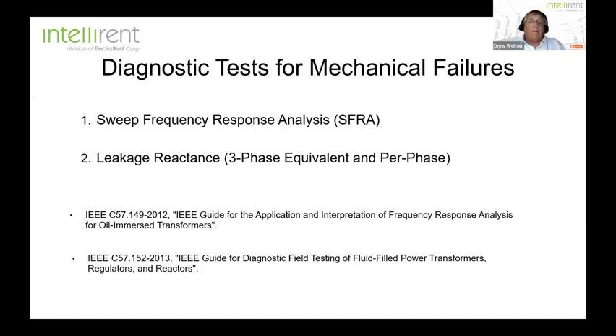All right, so let's say we've had a number of through faults and we've recorded this information, and we want to actually, during our next maintenance period when we're testing the transformer, see if there has been any physical damage associated with the transformer. And there's two types of tests you run for looking at mechanical failures. One, of course, is the SFRA, sweep frequency response analysis, and the other is your leakage reactance test.